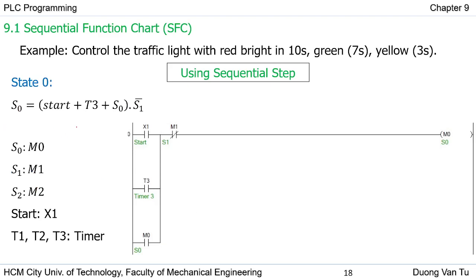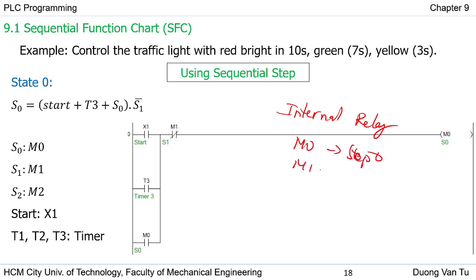We can use the conceptual design and apply it in the GX Work tool software to build the control program. In practice, when constructing the control program, we can use the internal relay. I use M0 for step zero, M1 for step one, and M2 for step two. We use internal relays because they are internal memory and do not affect any physical input or output, so we can use them freely. Internal relay memory is very useful for expressing the state of the control process.